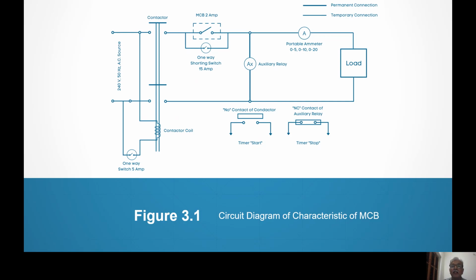Then what we have done? Across the supply, we have an auxiliary relay, which is a 230-volt relay, so it is getting a 230-volt supply. Its NO contact closes and it starts the timer, right? We have an ammeter, portable, with ranges 0-5, 0-10, 0-20, because we want to take readings in a large range, starting from 0.5. Often we would want to test not only a 2 ampere MCB but a 4 ampere, 5 ampere or 20 ampere MCB. Therefore, we need different ammeters. So the ammeters are there.